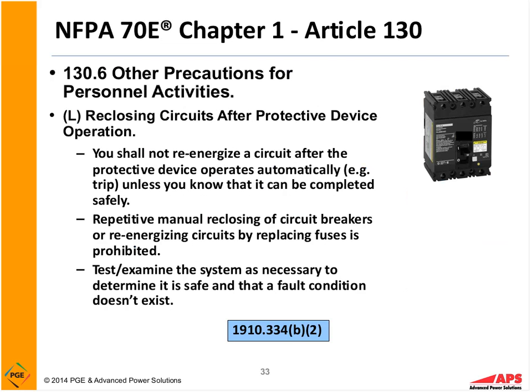If you do not know the cause of that breaker trip, or if you had a fuse blow, they're saying you cannot just go in there, put new fuses in, and reclose the fusible disconnect or close the breaker. A little example from a place I was just teaching at recently: the gentleman had a 1200 amp breaker trip. He went up to the breaker and reset it without doing any investigation. It blew about a 12-inch hole in the front of the switchgear and narrowly missed causing extensive damage to his body. So you can see that repetitive manual reclosing of breakers is prohibited.